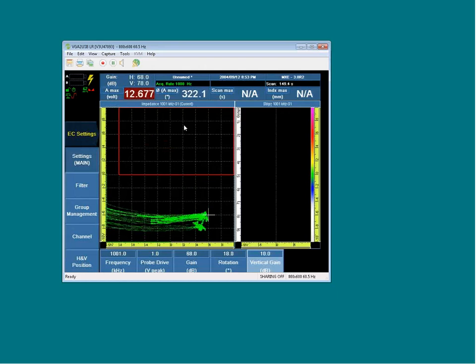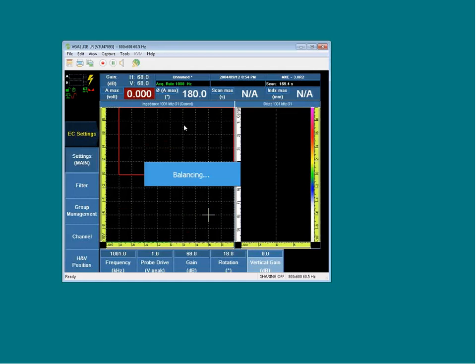and I'm going to show you the results on a carbon steel now. So the sample is identical. I'm going to explain a little bit in detail once I have the C-scan view, but I basically have a long notch and a few smaller notches. So I'm going to move to that carbon steel standard here, get rid of the vertical gain, otherwise I'll get lost if I don't, and re-null the system.